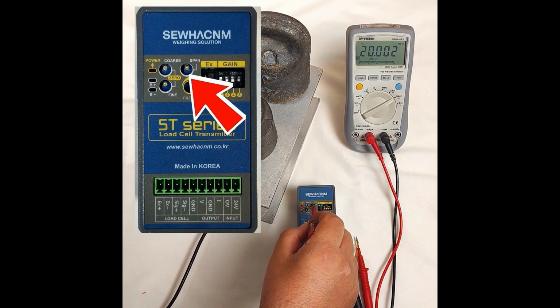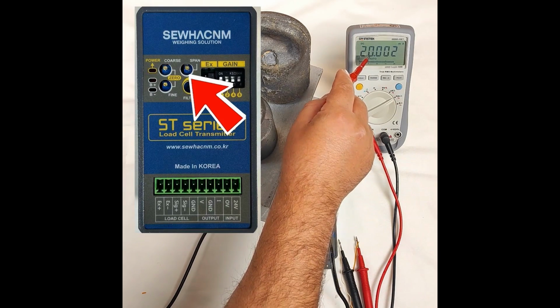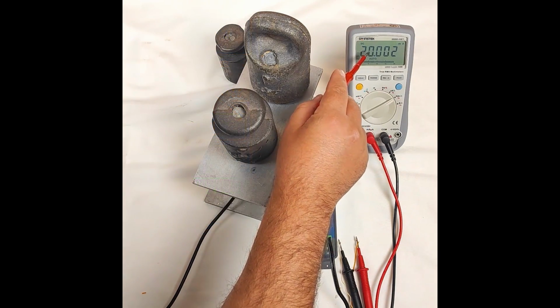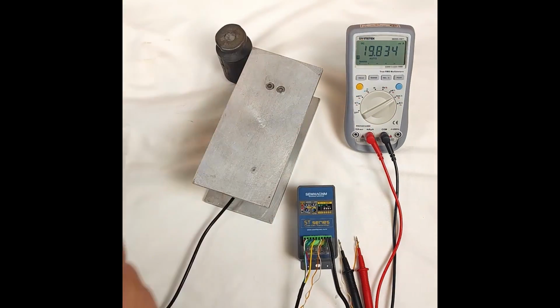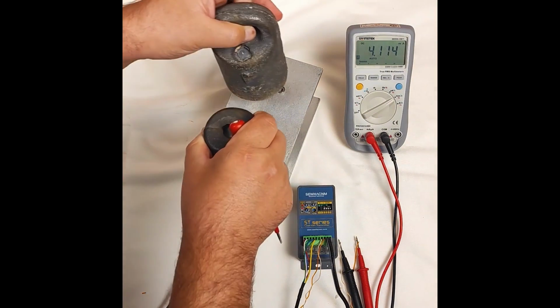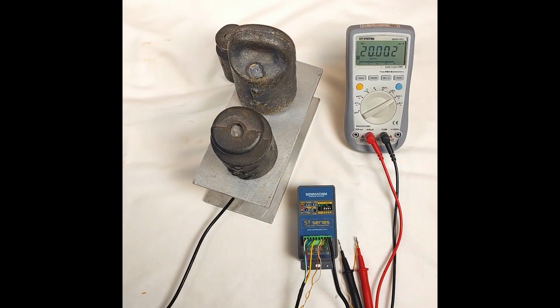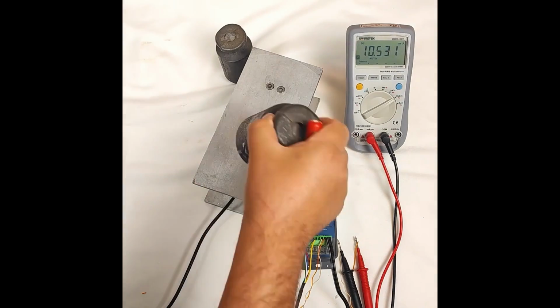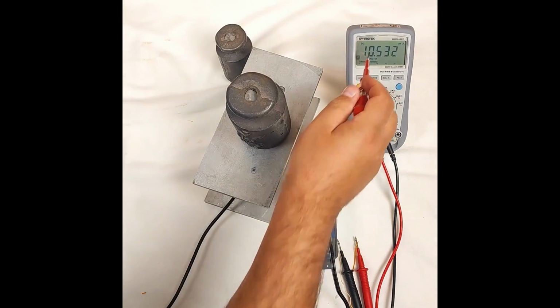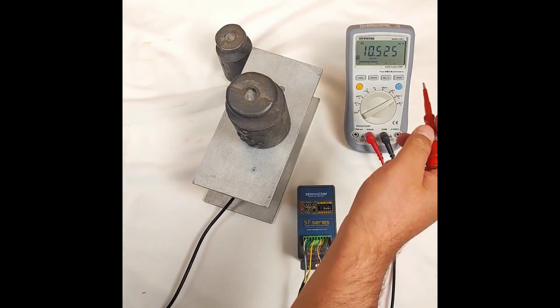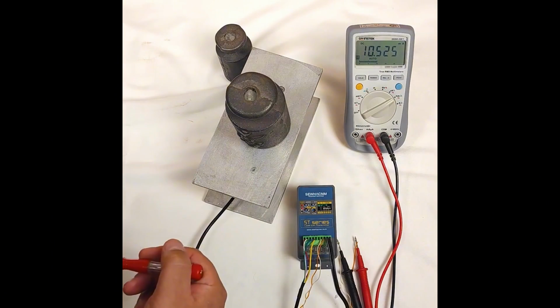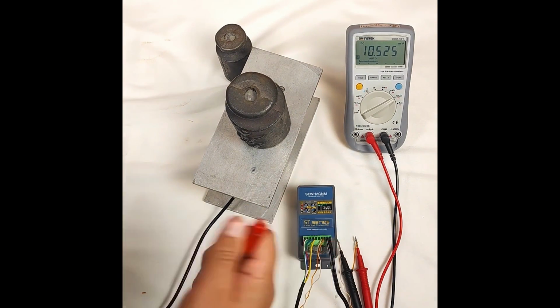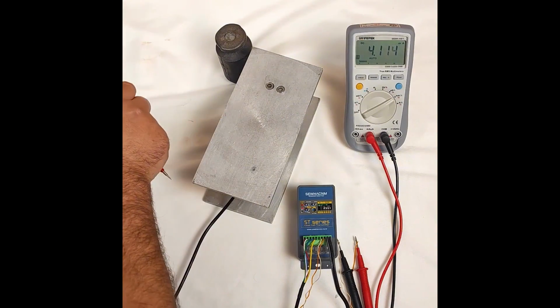Now, at this stage, we need to turn the span potentiometer until the multimeter shows 20 milliamps. So with no load, it shows 4, and at full load, it shows 20. For example, if I put a 2 kilogram weight on it, it shows 10, which means the scaling works linearly. This is essentially the calibration of the load cell transmitter.